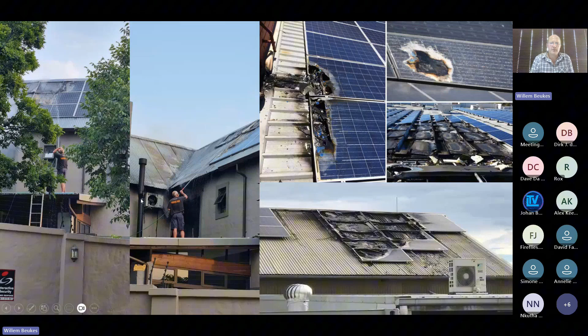Here are some scenarios on what happens and how fire propagation spreads on roofs for DC PV panels. On this middle section, you can see on these panels, there's no ventilation underneath the panel, no 100 mm ventilation. So these panels overheated. But the reason for this picture, I want to show you how far this flame propagated on the left, and actually burned up even the aircon on the side of this panel. So the flame propagation and arc forming on these panels are quite extensive. In most scenarios, the arc propagation and flame propagation goes up to 5 meters horizontally, where these panels then overheat or arc.